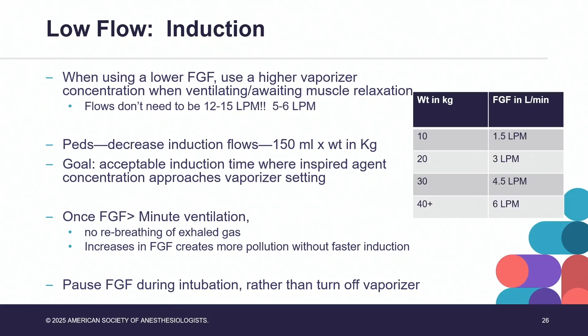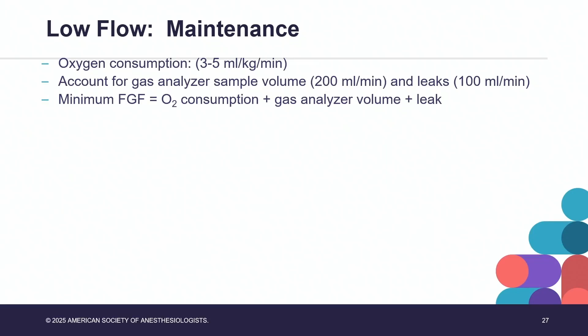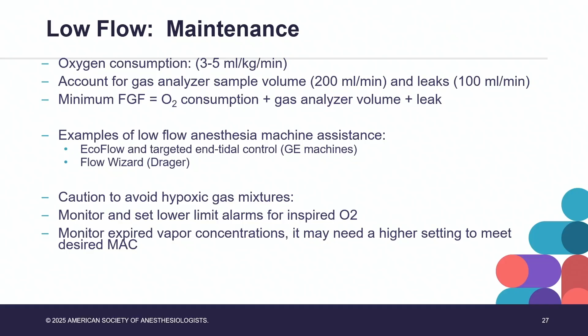During maintenance, you can figure out the oxygen consumption, so usually 3 to 5 mL per kilo per minute, and then you can take into account the gas analyzer sample of 200 and leaks of about 100, and then figure out what kind of flows you need during maintenance. There are some low-flow machine assistance: EcoFlow and targeted end-tidal control on GE machines, Flow Wizard on Draeger. You need to be careful to avoid hypoxic gas mixtures, however, so monitor and set lower limits for your inspired oxygen, and also watch your expired vapor concentration, knowing that you might have to set the vaporizer higher to achieve that MAC.